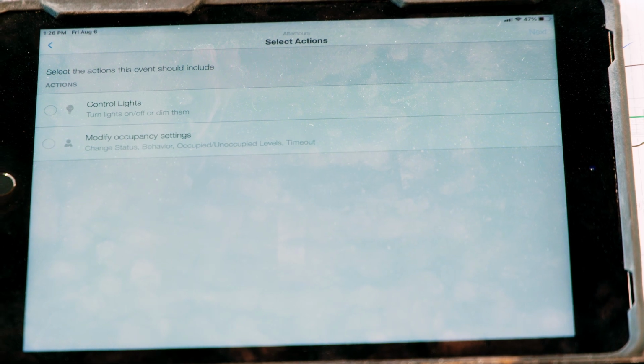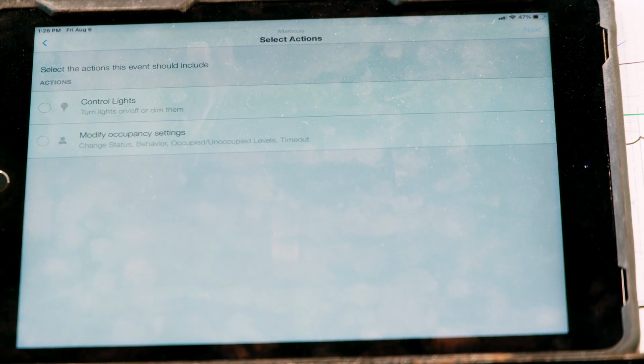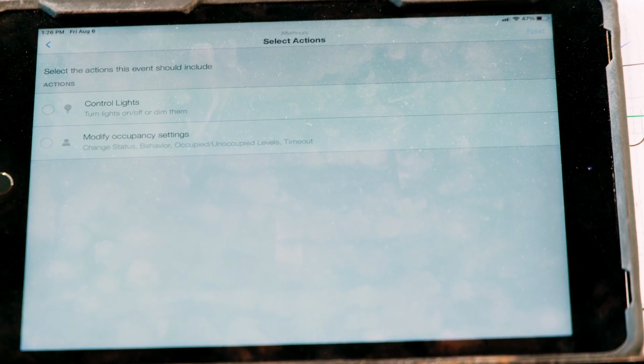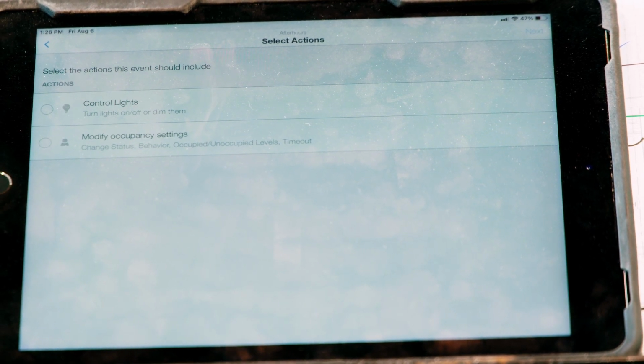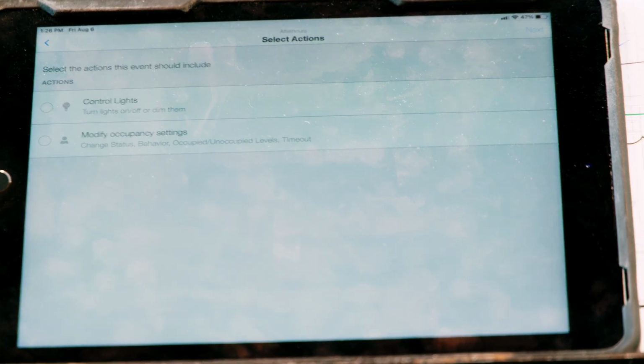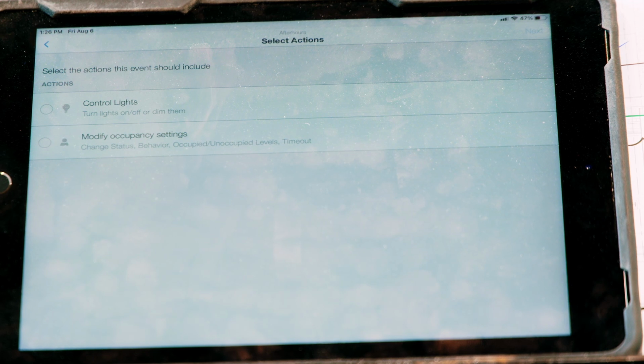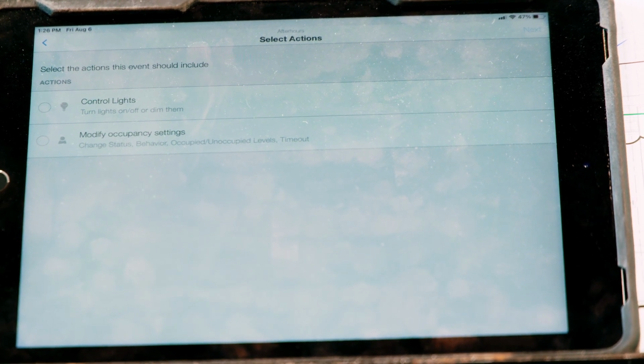So if it does go to that 10% and they get up and move around, it won't turn on unless they hit the Pico? No. Because once the occupancy sensor goes to unoccupied, the moment it senses motion, it goes back to occupied and sends a signal out. It's only that time in between, right?